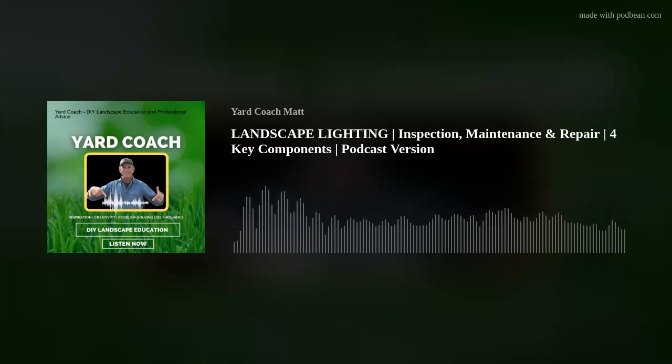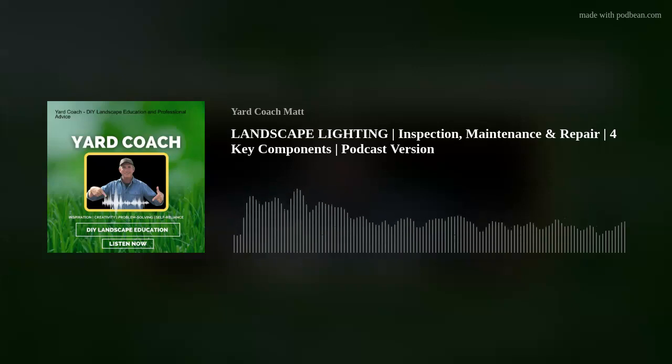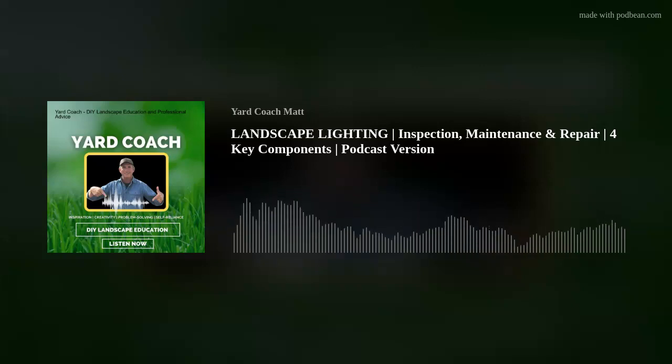Sometimes replacement is going to be required. Sometimes cleaning only will suffice. You can get fancy here too, like I did back at the transformer with you. You can get fancy here if problems persist with no bulbs coming on.